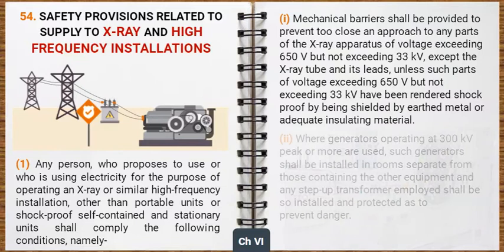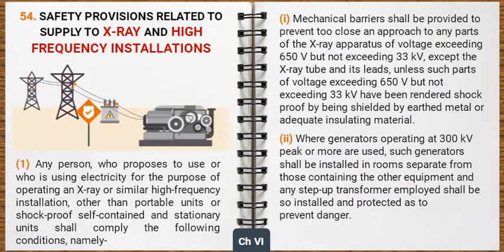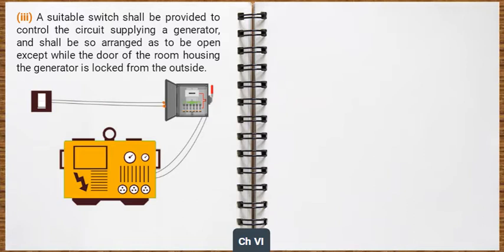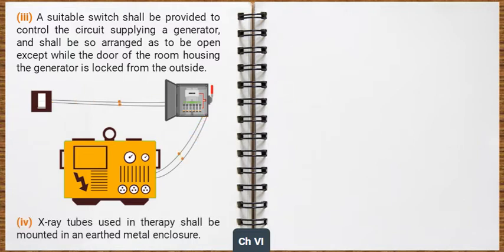Where generators operating at 300 kV peak or more are used, such generators shall be installed in rooms separate from those containing the other equipment, and any step-up transformer employed shall be so installed and protected as to prevent danger. A suitable switch shall be provided to control the circuit supplying a generator and shall be so arranged as to be open except while the door of the room housing the generator is locked from the outside. X-ray tubes used in therapy shall be mounted in an earthed metal enclosure.